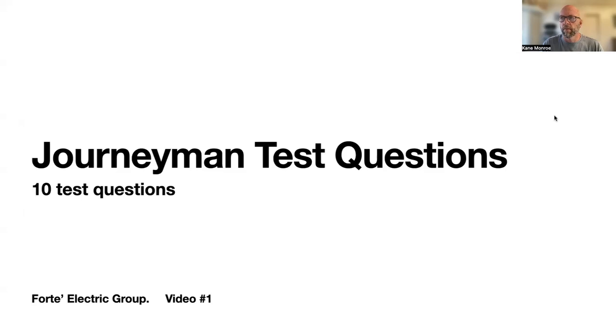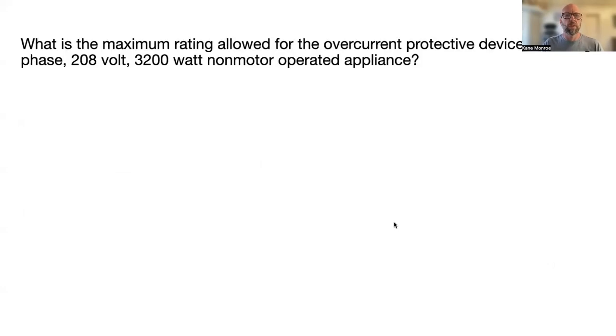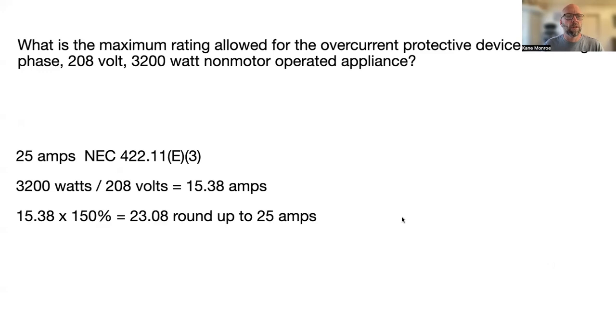We've got 10 questions — this is video number one. First question: what is the maximum rated overcurrent protection device rating allowed for a single-phase 208-volt 3200-watt non-motor-operated appliance? That's a lot of verbiage. The answer is 25 amps.